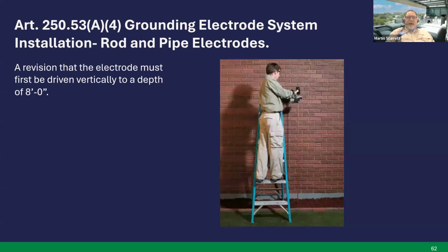250.53(A)(4), grounding electrode system installation, rod and pipe electrodes. In the previous code, like 2023, whenever you're installing a ground rod, you're supposed to first drive it 8 feet, and if you encounter rock, then you could drive it at a 45-degree angle, and then if you encounter rock, then you can bury it. But a lot of people jump straight to the 45-degree or the bury it. But the revision in the new code said it must be driven first at 8 feet. So you have to attempt to drive it vertically first, then go to the other methods. But it's always kind of said that. It just spelled it out more now.